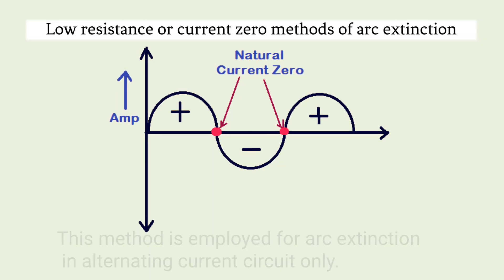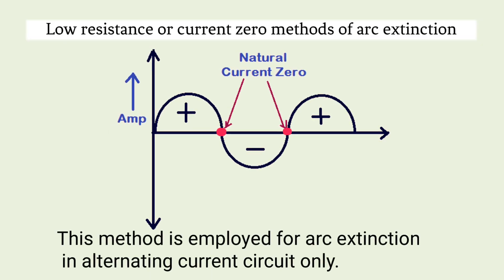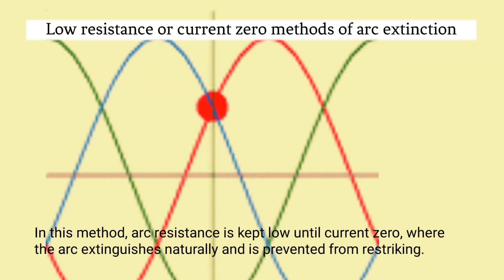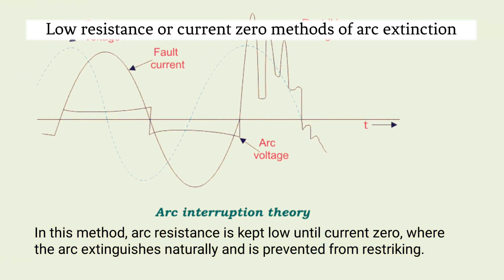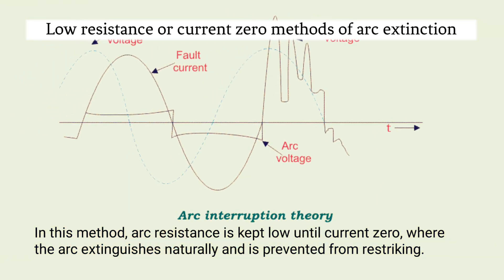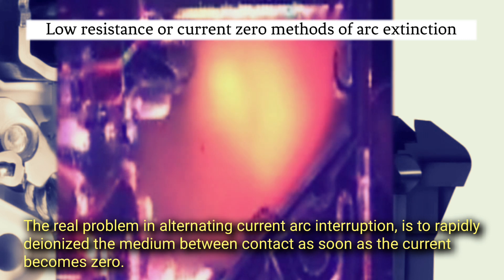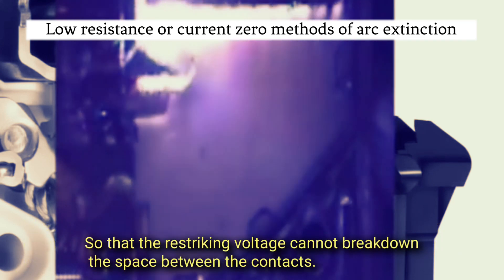Low resistance or current zero method. This method is employed for arc extinction in alternating current circuits only. In this method, arc resistance is kept low until current zero, where the arc extinguishes naturally and is prevented from restriking. The real problem in alternating current arc interruption is to rapidly de-ionize the medium between contacts as soon as the current becomes zero, so that the restriking voltage cannot break down the space between the contacts.